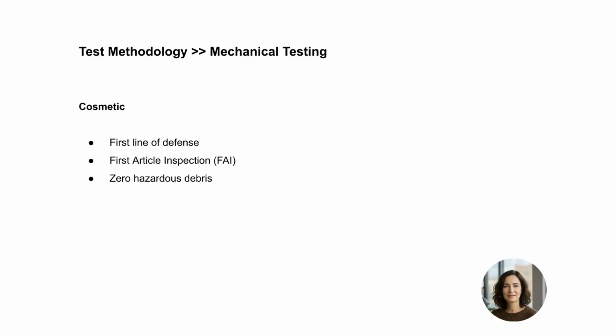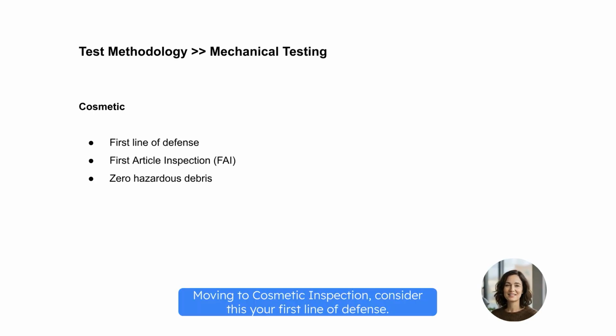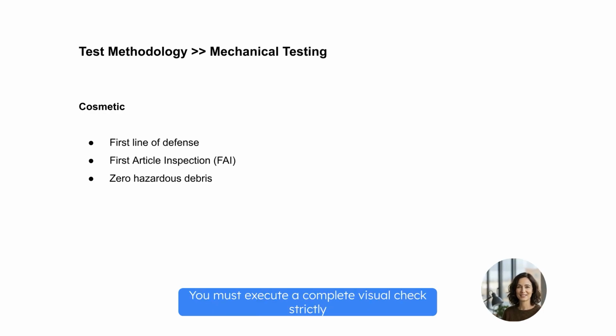Moving to cosmetic inspection, consider this your first line of defense. It goes beyond simple aesthetics. You must execute a complete visual check strictly following the first article inspection, FAI, criteria. Your target is specific. Verify the physical specs and ensure there is absolutely zero hazardous debris or FOD hiding in the unit. If you see manufacturing waste, the unit fails.